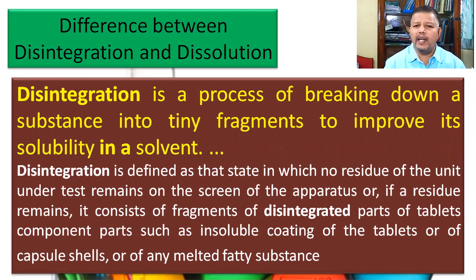Disintegration is also defined as that state in which no residue of the unit under test remains on the screen of the apparatus, or if a residue remains, it consists of fragments of disintegrated parts of the tablet component, such as insoluble coating of the tablets or the capsule shell, or any melted fatty substances present in the tablet or in the drug.